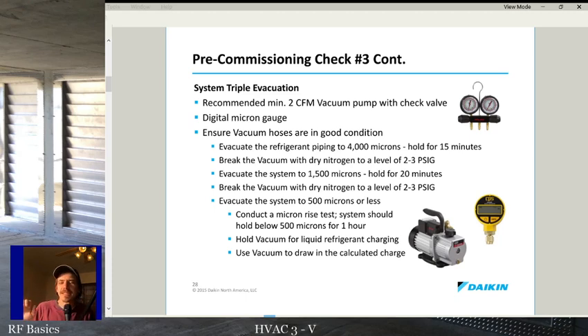I mean, all it takes is some temperature change, right? And your rubber gasket changes a little bit. It expands or contracts, and then you've got a leak. Came back to a smoking vacuum pump. Yeah, I mean, it's crazy, dude. The first VRF system I did, we ran 2 vacuum pumps on it for a weekend to get down to where we did. And we got that thing down tight and it held way below 500 microns. But it was tough, right?